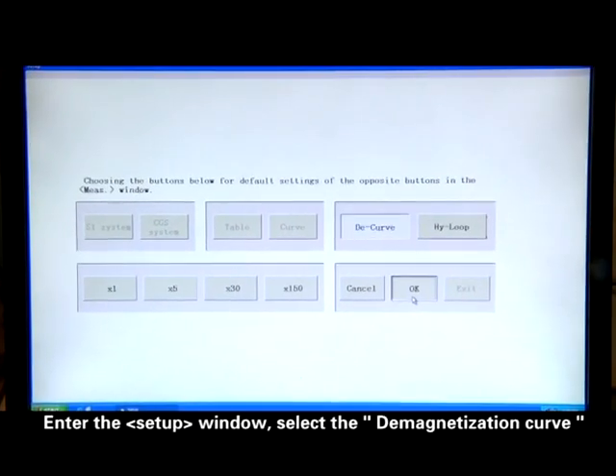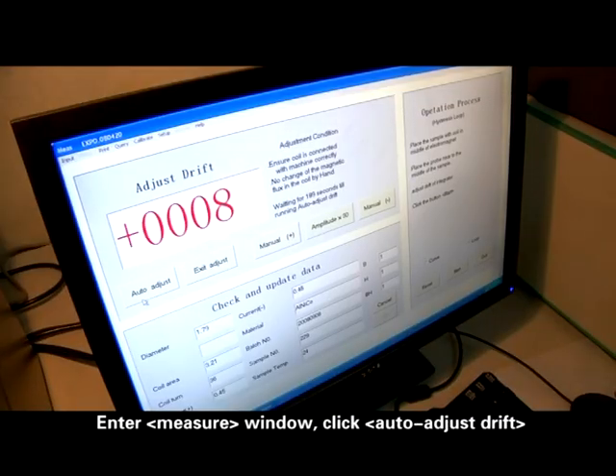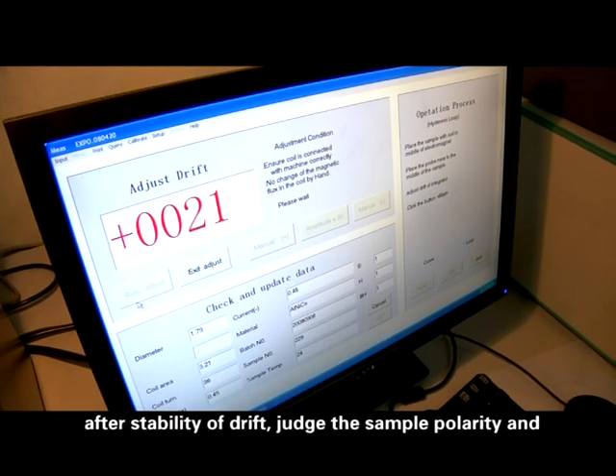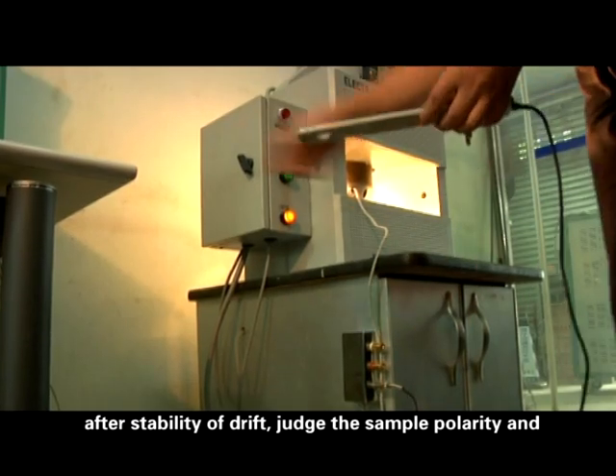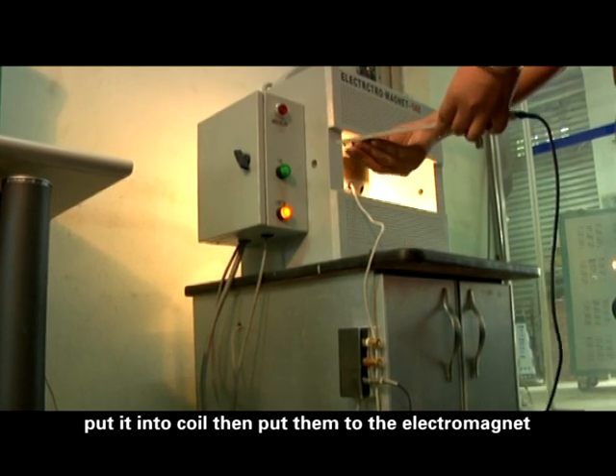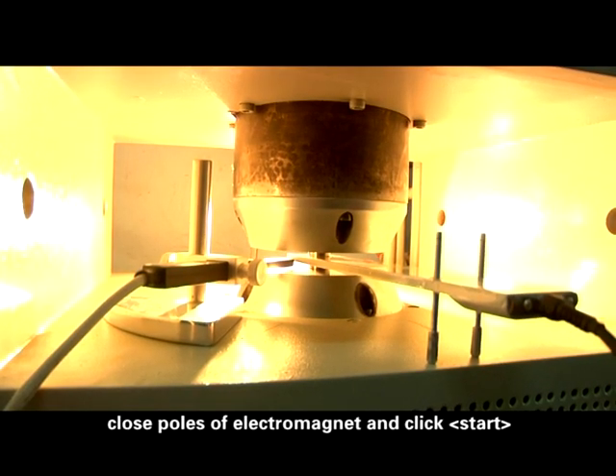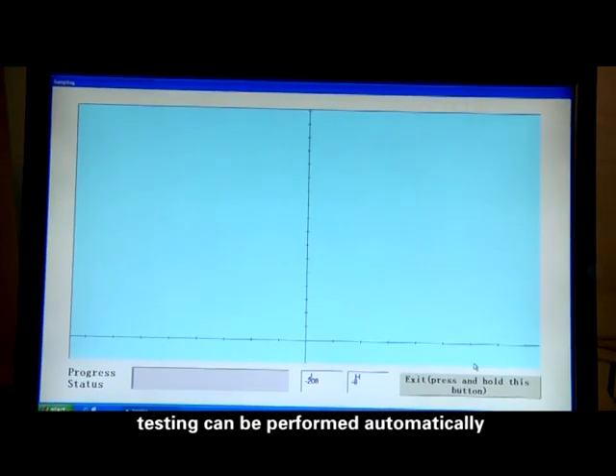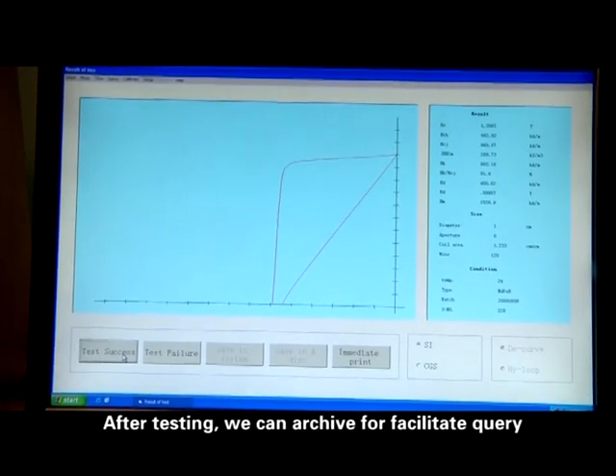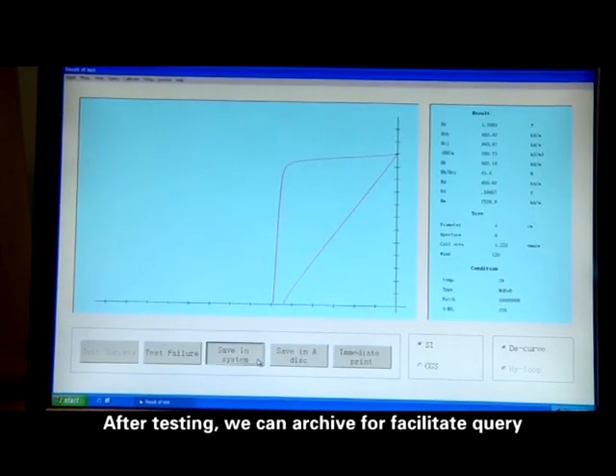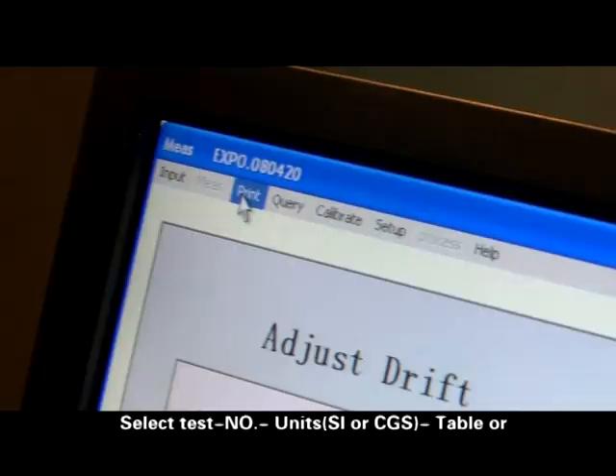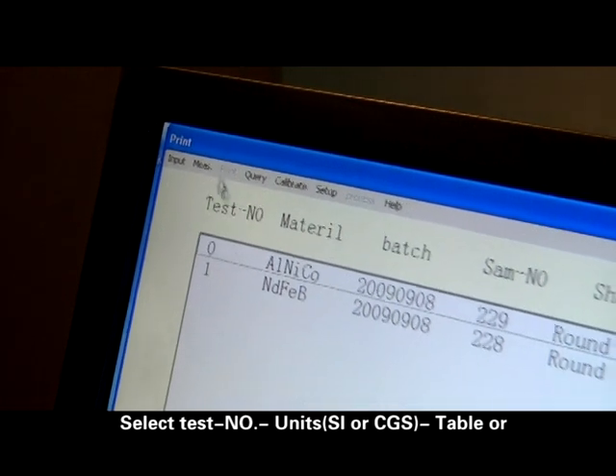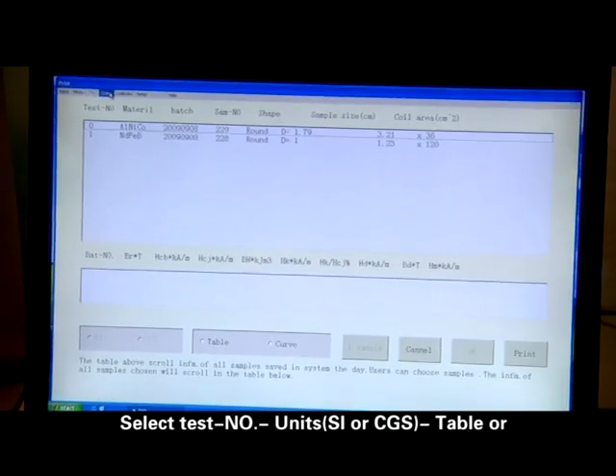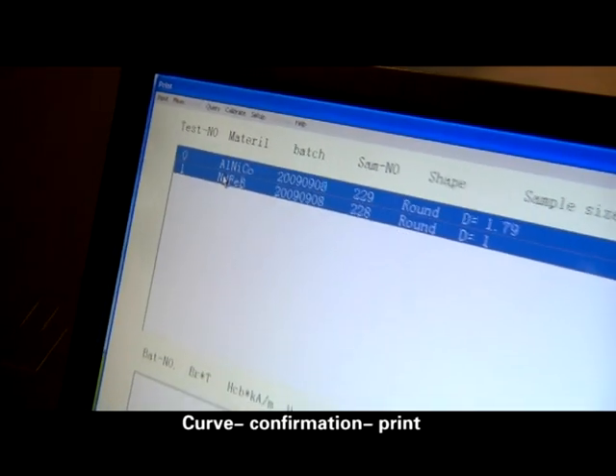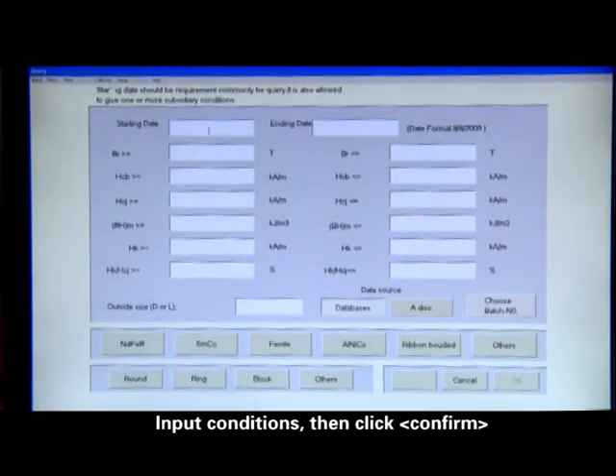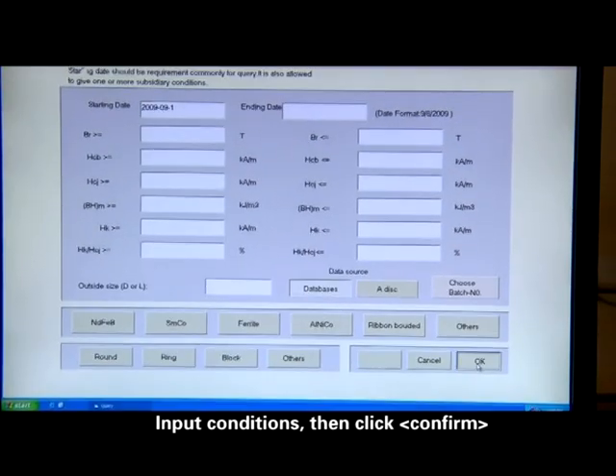Enter the setup window. Select the demagnetization curve. Enter measure window. Click Auto Adjust Drift. After stability of drift, judge the sample polarity and put it into coil, then put them to the electromagnet. Close poles of electromagnet and click Start. Testing can be performed automatically. After testing, we can archive for facilitating query. Print. Select test, number, units, SI or CGS, table or curve, confirmation, print. Query. Input conditions, then click Confirm.